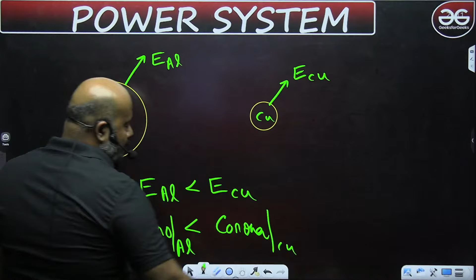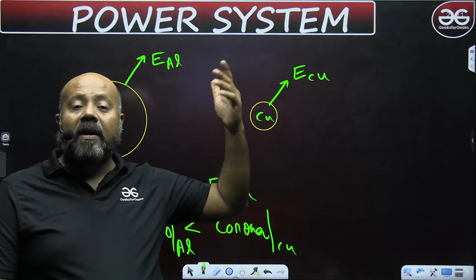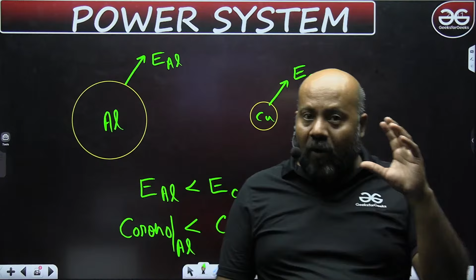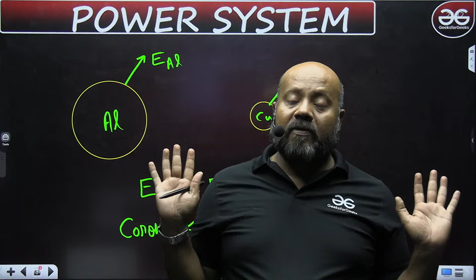Now corona is a very important phenomenon, and the losses are going to be very significant when you talk about very high voltages and very long transmission lines. So when you talk about long distances and high voltage lines, the losses due to corona become very significant. This is one important reason why we don't go for copper, we go for aluminum conductors.